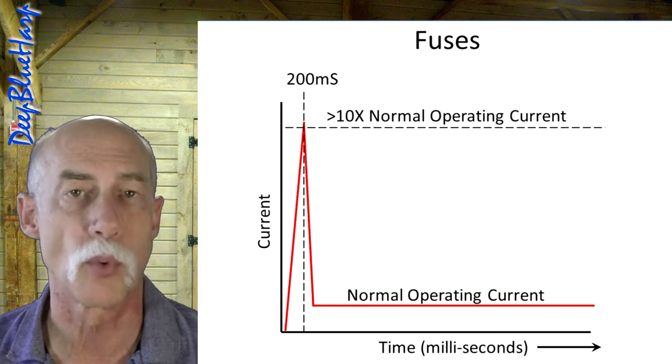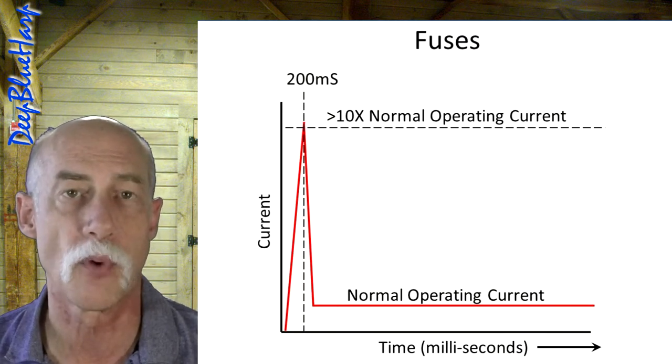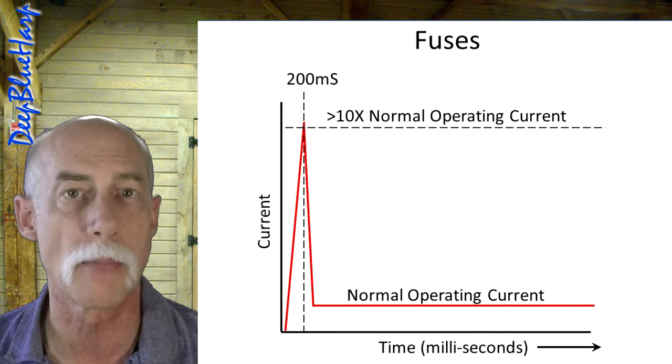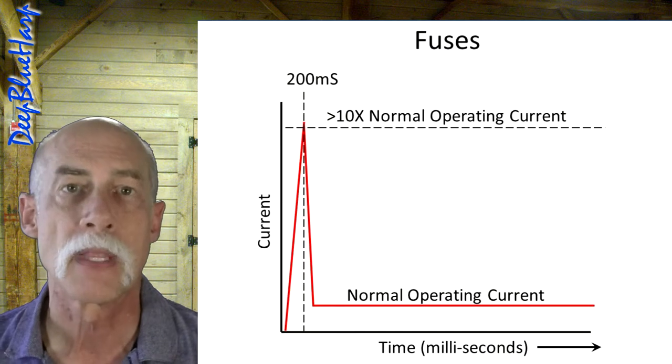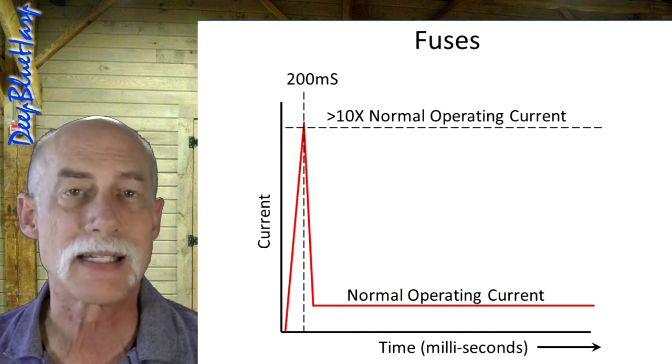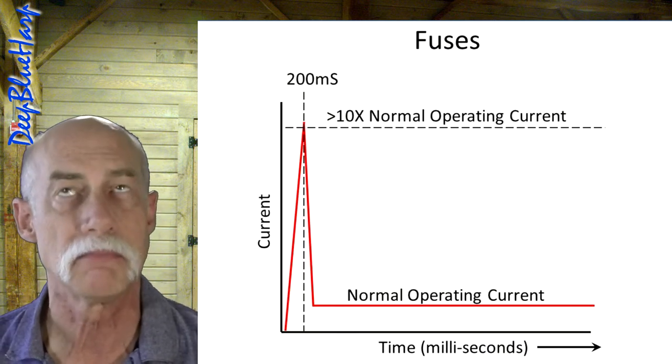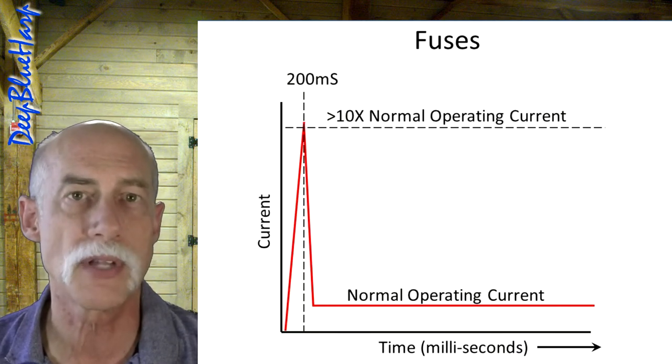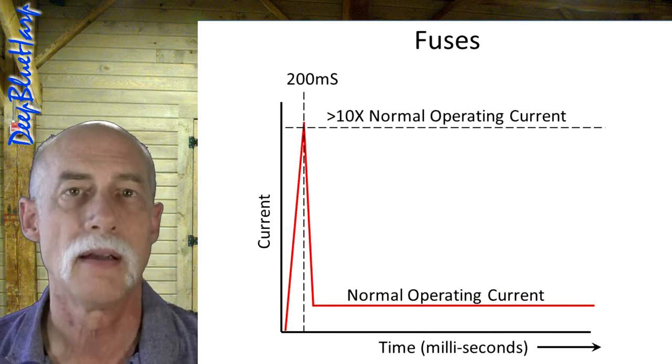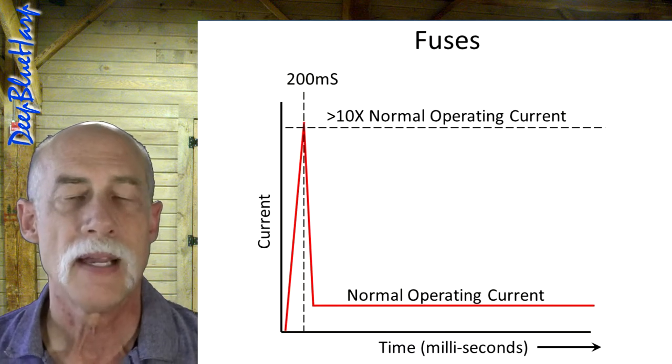In other words, if you're needing one amp for continuous normal operating current, as soon as the unit is switched on, it will draw at least 10 times that, roughly. For a moment, for about 0.2 seconds, it has to withstand 10 amps. That's a lot.